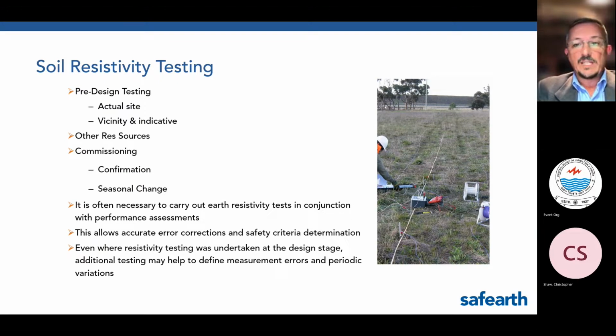Let's talk about another traditional test. Perhaps the most common of the traditional tests is to do soil electrical resistivity testing. This is a very important test. It's even more important to do it with an understanding of what the test results are going to be used for, taking into account things other than just the electrical measurement, things like geology, geography, visual clues in the area as to what kind of stratification or what kind of conductive interferences could be there. All those things help you form the right electrical model for the soil. And that model or a set of models is essential for designing and sometimes for testing analysis.